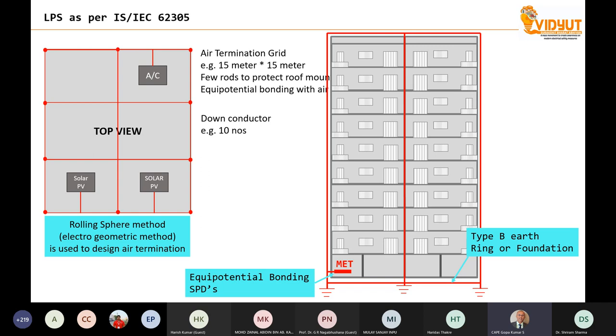Now the first part of lightning protection is to create an air termination system. An air termination system is intended to intercept the lightning. In the sense, instead of hitting the building, the lightning is supposed to hit this particular air termination. There are two or three ways of designing the air termination. If you have a flat roof, what is recommended is a grid, say, for example, 15 meter by 15 meter.